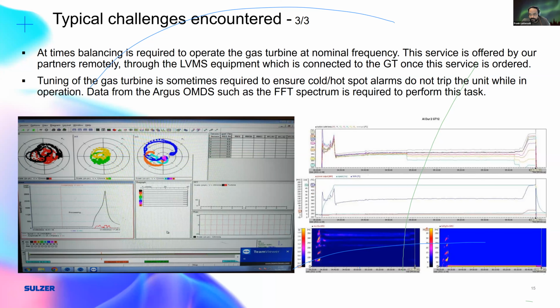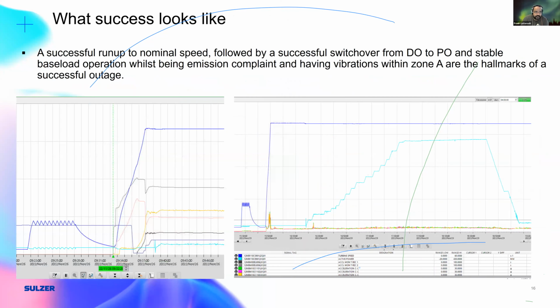So what does a successful completion of the job look like for me? When I start, in this case, you can see there is a purge cycle. So the purge cycle, you operate your generator as a motor, where you introduce current to turn the rotor, and you do that to allow a certain amount of air through the whole system, compressor, chamber, and turbine, because you want to make sure there are no explosive gases trapped in the system. This is actually a safety requirement, and if you have a boiler, your purge time is usually much longer than if you have an open cycle, okay?